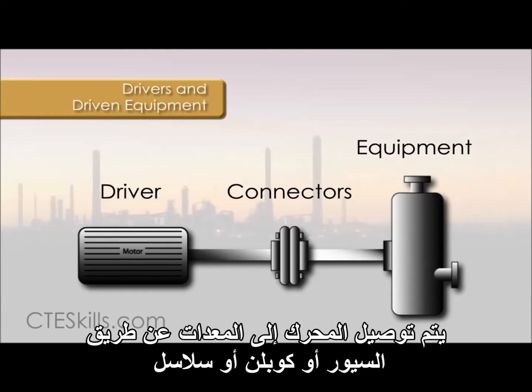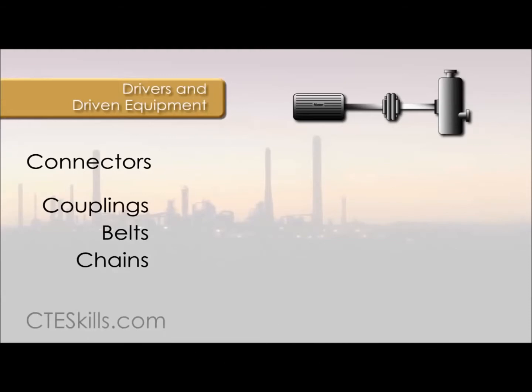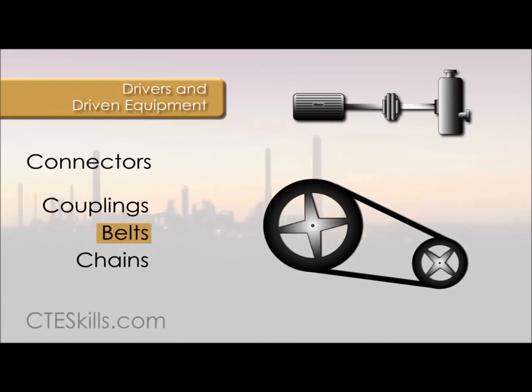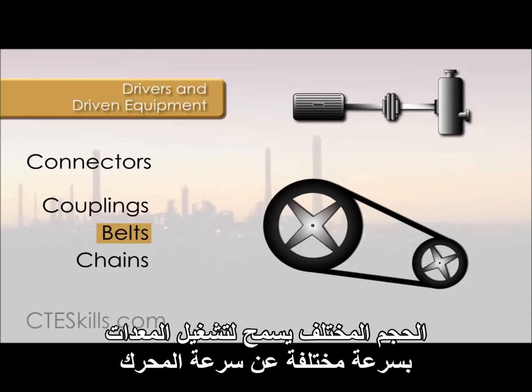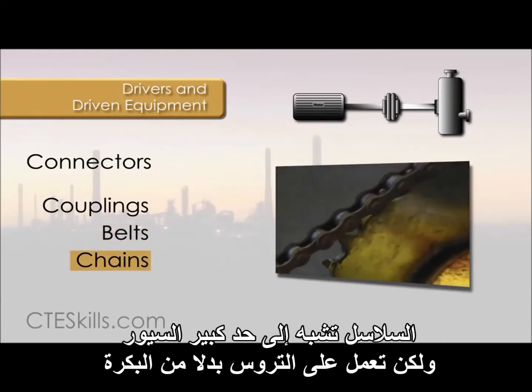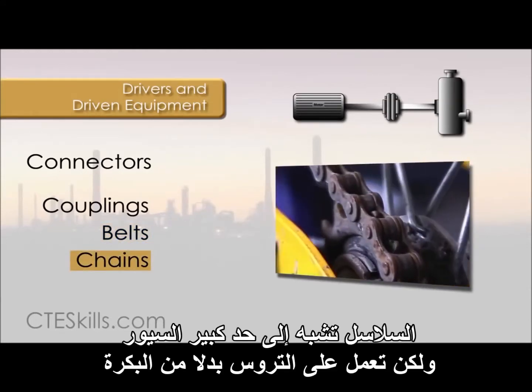The drivers are connected to the equipment by couplings, belts, or chains. Belts operate on a pulley system. They connect two parallel shafts. The size of the pulley determines the speed. Different sizes allow the equipment to operate at a different speed than the driver. Chains are quite similar to belts, but operate on a series of sprocket wheels instead of a pulley.